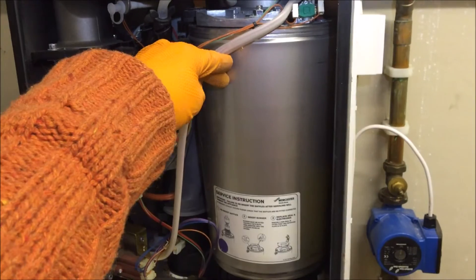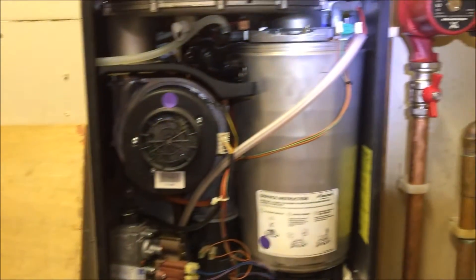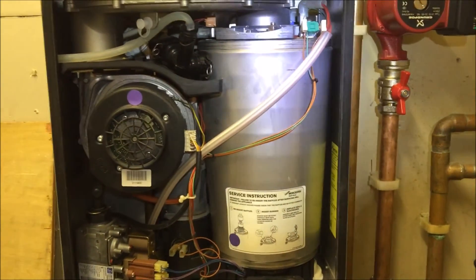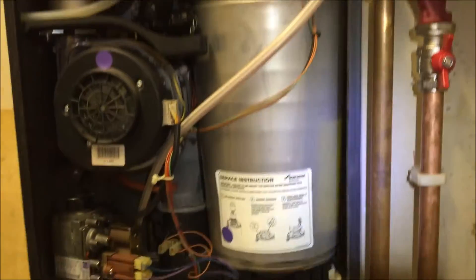Here's a good example of what I'm talking about. This is the heat exchanger on the other boiler and as you can see it's smooth. If I pan round to this one, you can really see the lines — the internal fouling and scale buildup compared to the clean one.